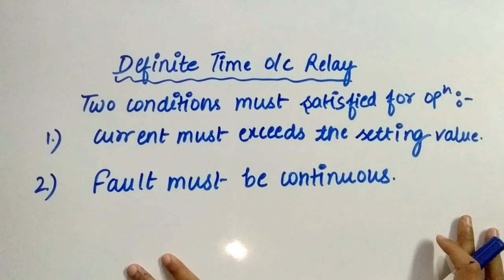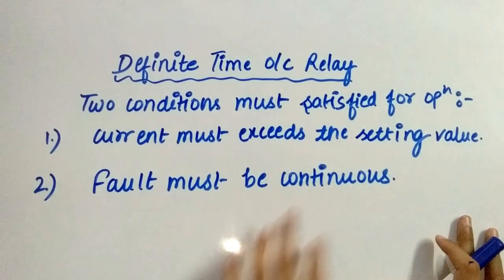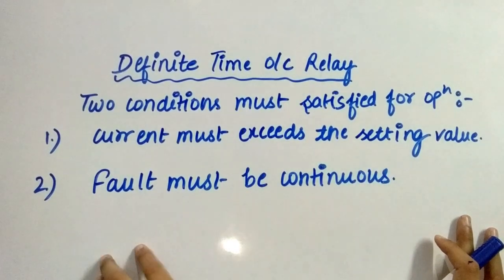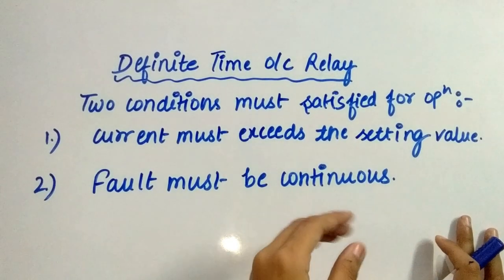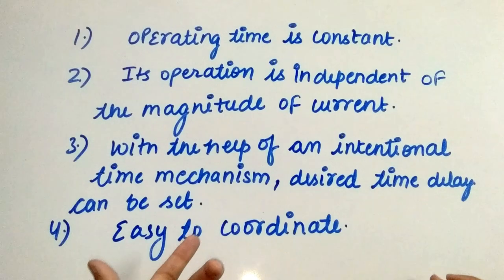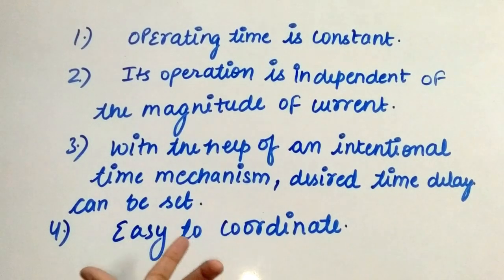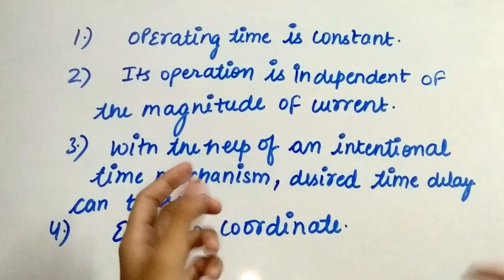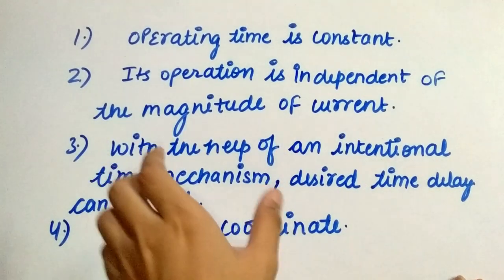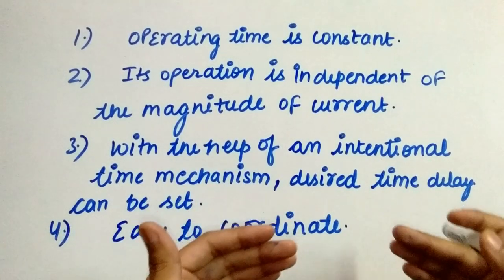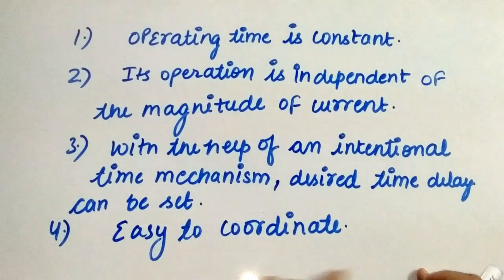In a definite time overcurrent relay, two conditions must be satisfied for operation or tripping. The first condition is that the current must exceed the setting value. The second condition is that the fault must be continuous for at least a time equal to the time setting of the relay. Modern relays contain more than one stage of protection, and each stage includes its own current and time setting. The operating time is constant and independent of the magnitude of the current above the pick-up value. There is a pick-up value and time dial settings, and the desired time delay can be set with the help of an intentional time delay mechanism. It is easy to coordinate.